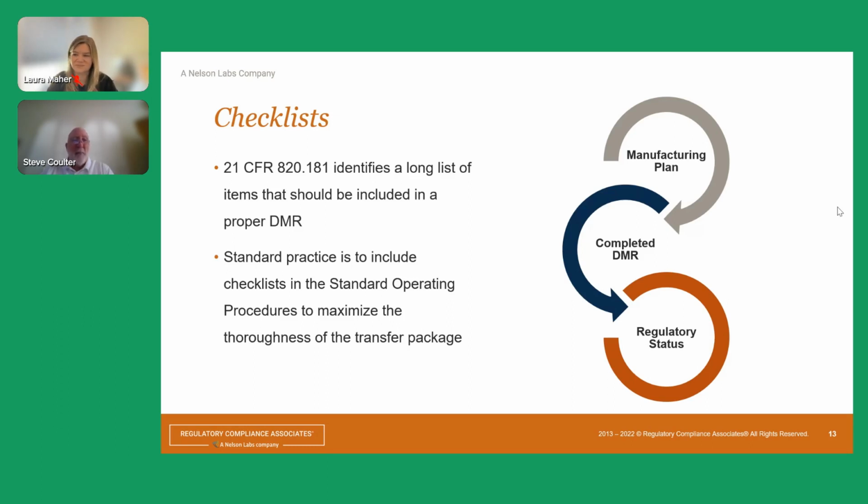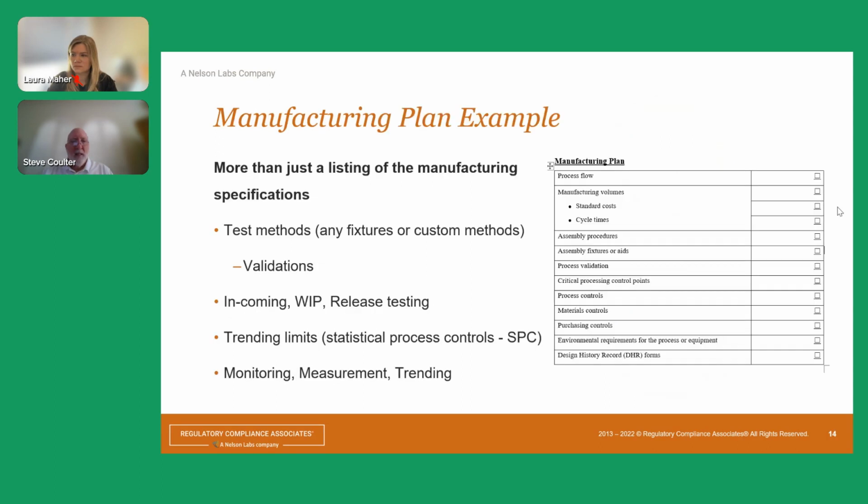But in the meantime, build your practices with safety nets. And that's what these checklists are, safety nets. These typically are lists, not details. So I'm not going to regurgitate documentation from everywhere, but what I am going to do is have an index that tells you where to go follow these things. So you have manufacturing plans, you have quality plans, you have regulatory plans. These are the plans that go into the early phase planning in the design history file.